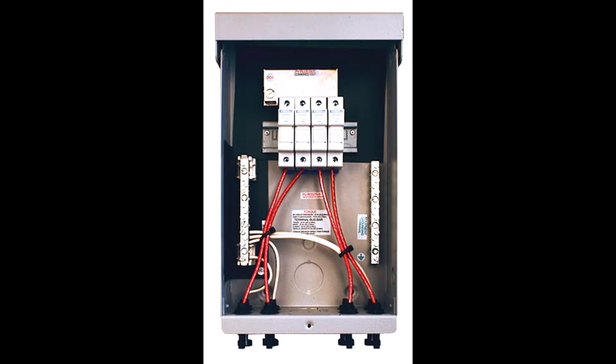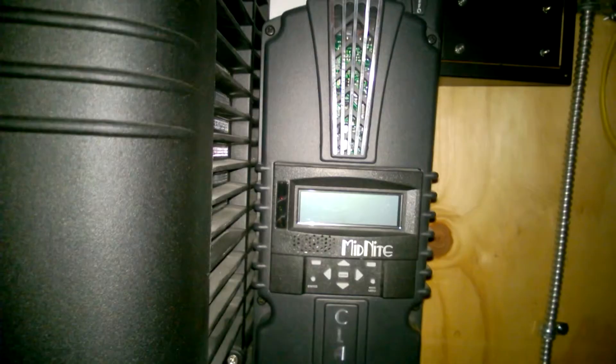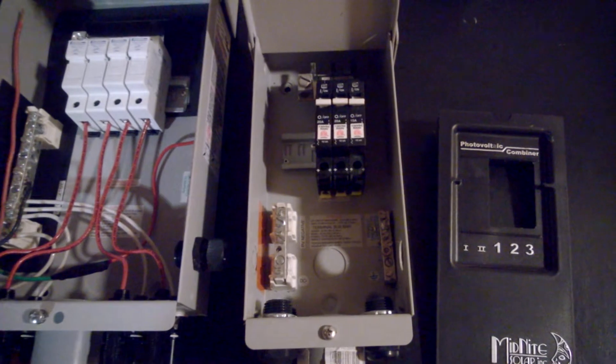First thing, we just cut the breakers off at the e-panel coming in and going out to the charge controller. I got out there at night with a light and unplugged the MC4 connectors to all the solar panels going to the old combiner box, unwired everything, and here it is next to the new one, which is a pre-wired MNPV-4 MidNite Solar combiner box.